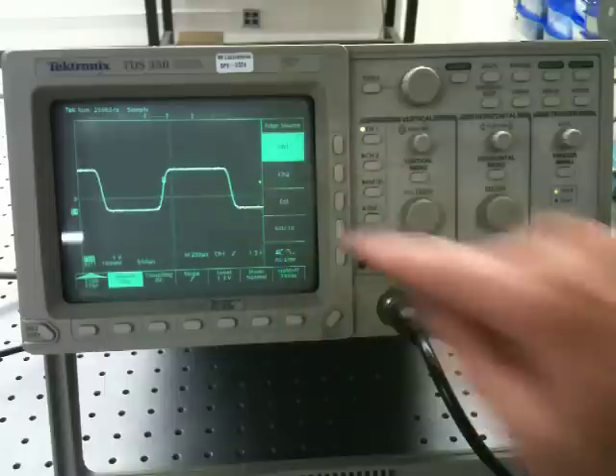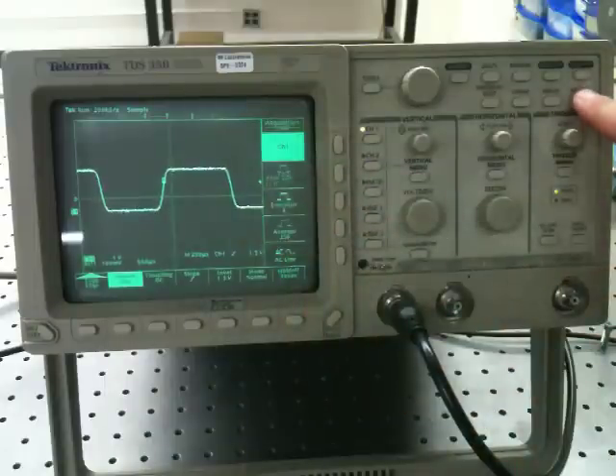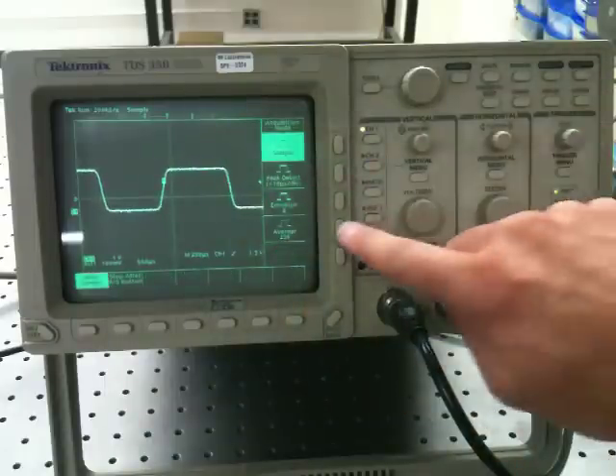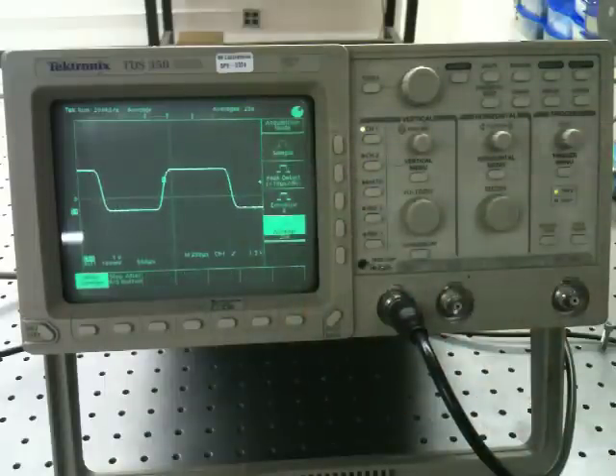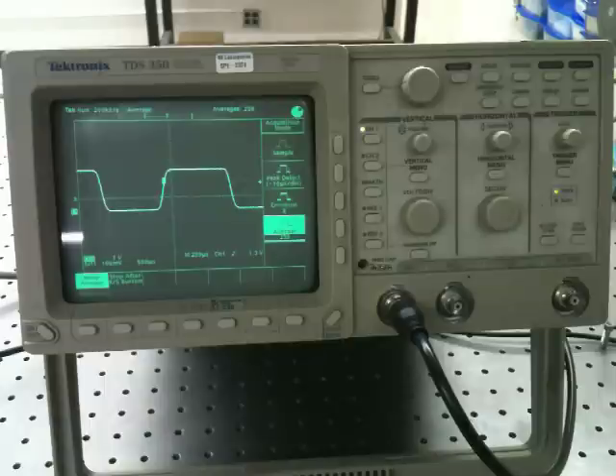I may see a little bit of noise. I can always go into the acquire menu and average if I have a nice stationary waveform, and that will take care of a lot of the noise for me.